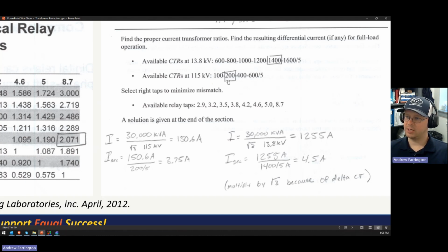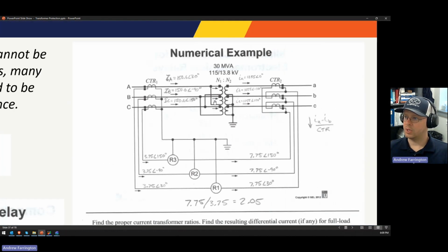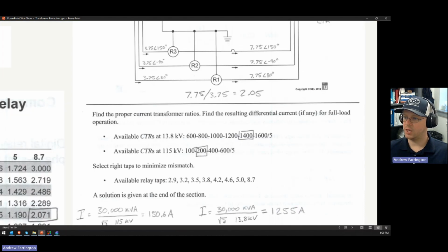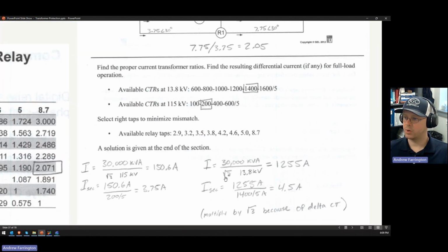Once you've selected that CT ratio, you can then do the same thing for the low side. So you can take the 30 MVA divided by the square root of 3 times the low side voltage rating, and then you get 1255 amps in this example. And then again, you'd select the next highest CT ratio, which is 1400 to 5.